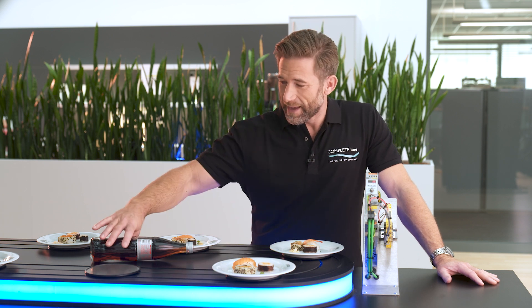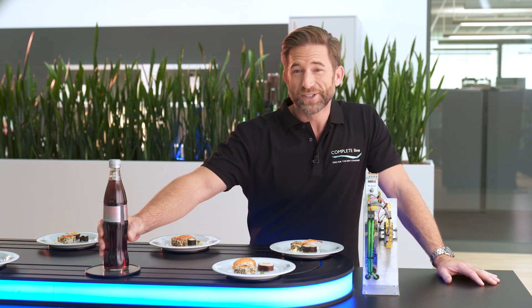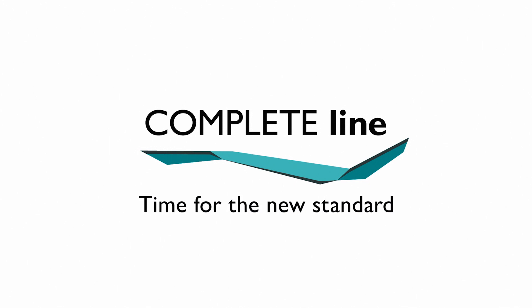And this is exactly what I want to show you now as we come back to our conveyor belt. I just need to adapt the ramp-up time, and if I give it a second try — voilà, the bottle remains standing. With Contactron speed starters, it's that easy. Thank you.